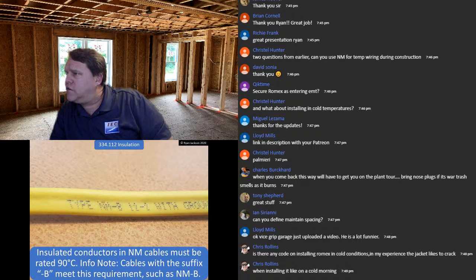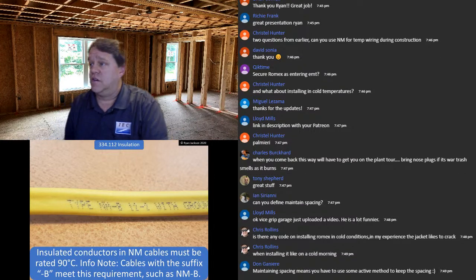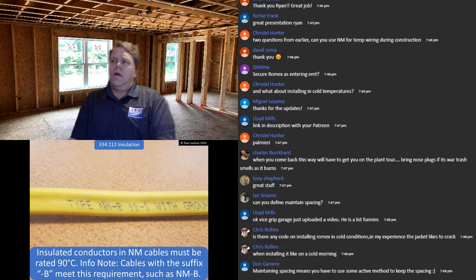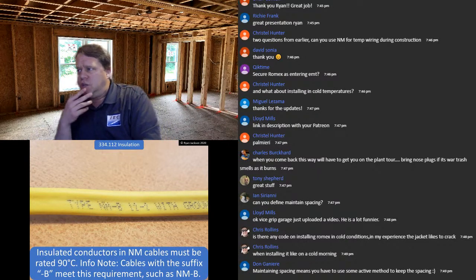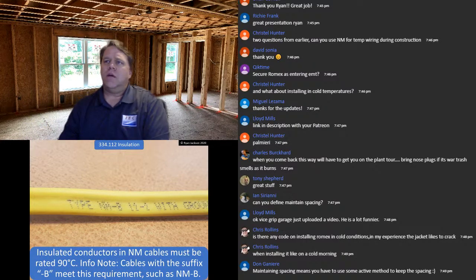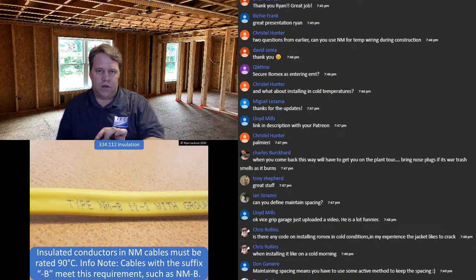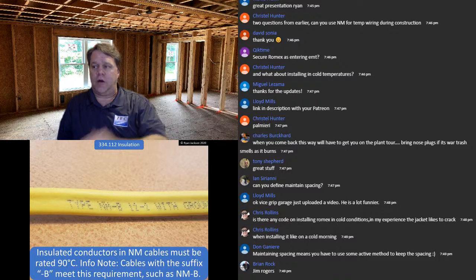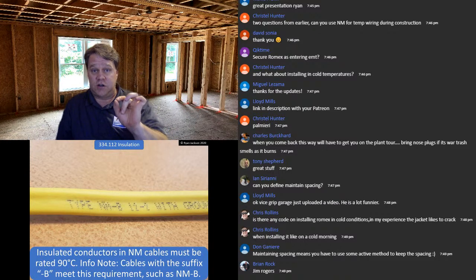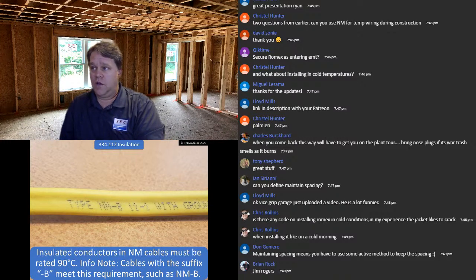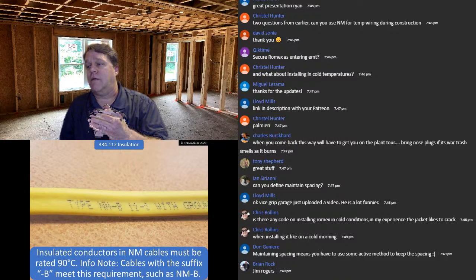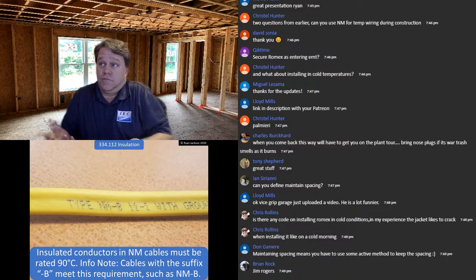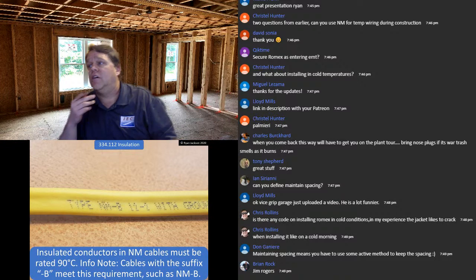Any issues on installing NM cable in cold conditions? No, I don't think there's any restrictions. There's certainly no code requirements. Let me say this though. If you go to 110.11, second paragraph, there is a specific section that says that you can use any wiring method during the course of construction, but it's not allowed to get damaged. So you're not allowed to have your NM cable damaged during the course of construction. There you go. So really, that's the only rule. It doesn't tell you how to deal with that.